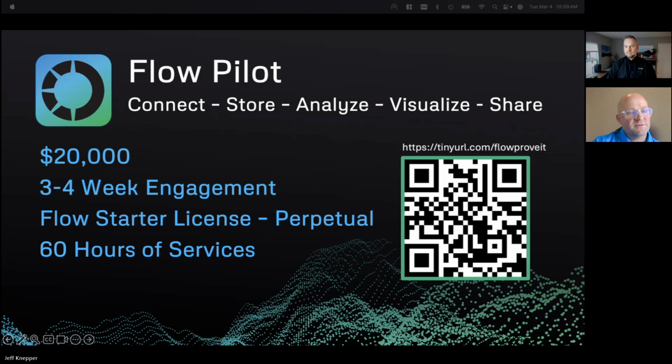Another design capability that we added into the product is exactly that as well. We don't want to go and query a historian for days and days and months' worth of data when we're backfilling or creating some of it. So inherently in the product, we've designed capability to batch backfilling. We will not hit a historian to give a year's worth of data. If I want to do that, we will batch it into chunks.